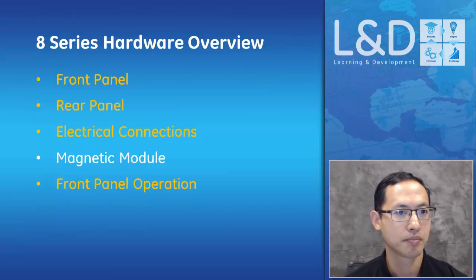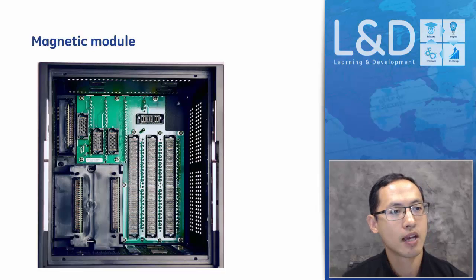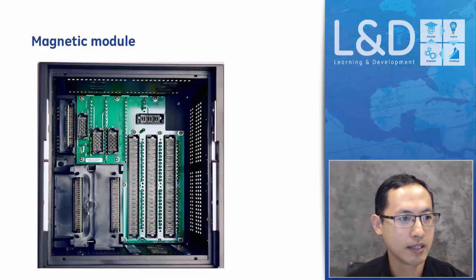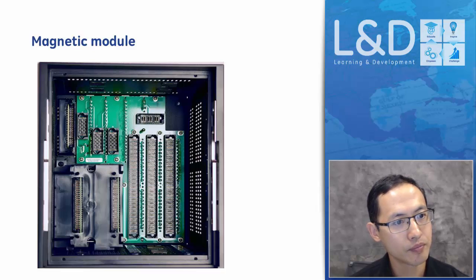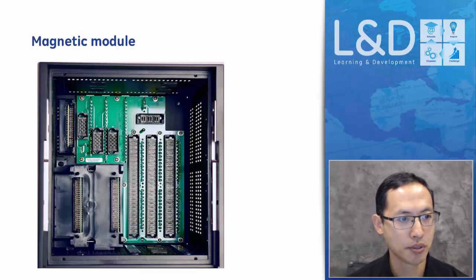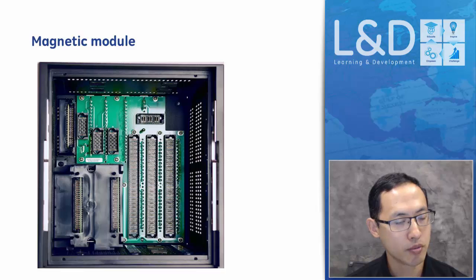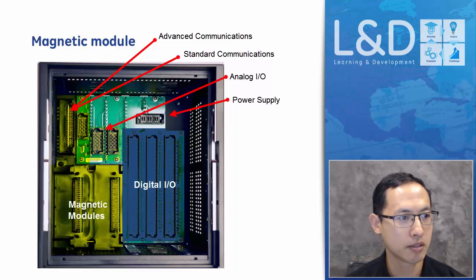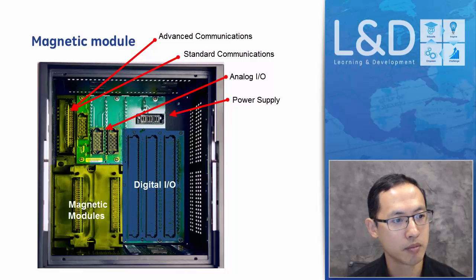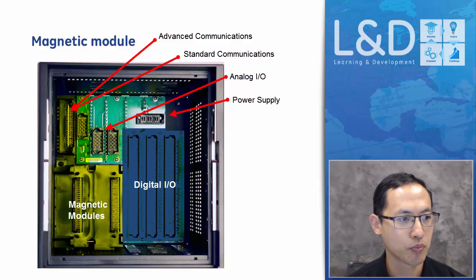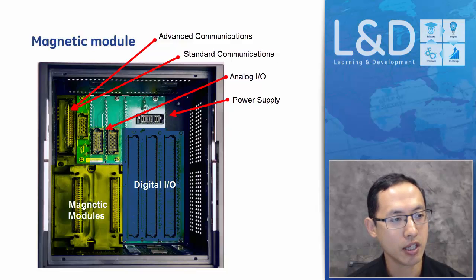Magnetic modules. So let's take a look inside the case of the 850 relays, so we can quickly identify each slot: the high voltage modules and the power supplies, low voltage modules for the RTDs, and the communication ports for the basic communication and advanced communication fiber optical connectors. And we see at the bottom left there's the magnetic module, which has the CT, VT inputs, for the J card and K cards.